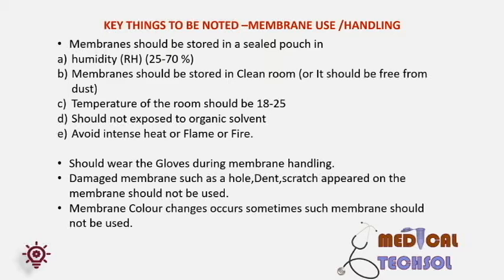Follow the instructions given by the manufacturer or supplier for the specific membrane. If the membrane is touched with bare fingers, finger impressions may appear and sweat or protein on the skin may be absorbed by the membrane, which may interfere with the assay — that is why gloves should be worn during membrane handling. Sometimes during operation, holes, dents, or scratches are visible on the membrane; such damaged membranes should not be used. During long storage, membrane color may change to yellow — such membranes should be rejected for production.